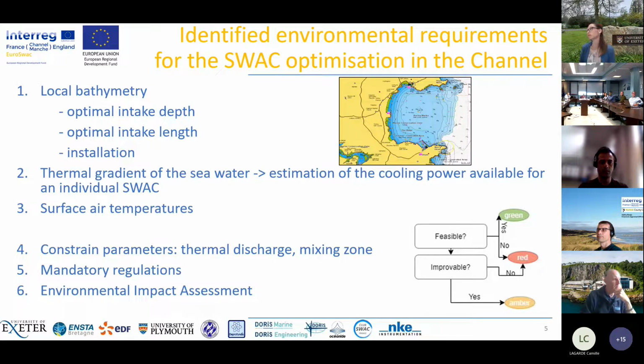We identify three main factors: local bathymetry, because based on the bathymetry we look into the optimal intake depth, optimal intake length, and also the geometry of the bottom of the channel where it would be installed. Then the thermal gradient of the seawater, needed to estimate the cooling power available for the individual SWAC, and also the surface air temperature. These are the three most important, but of course we look at other things too.